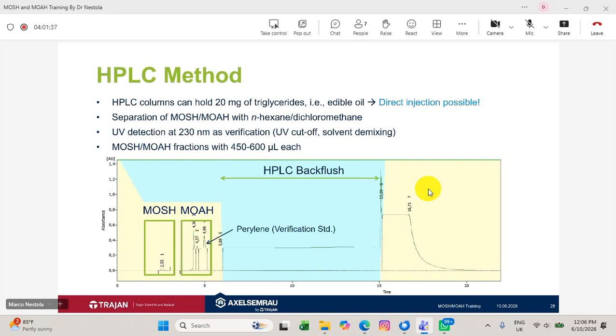Of course, first of all, you should not even get into this situation. Therefore, you might have noticed, and when we look in front of the instrument, we will see it, we also have an HPLC pre-column. So typically, this is where the junk should stick in the first place. What I have observed is many people just do not exchange the pre-column because we typically do not have many problems with higher back pressures.